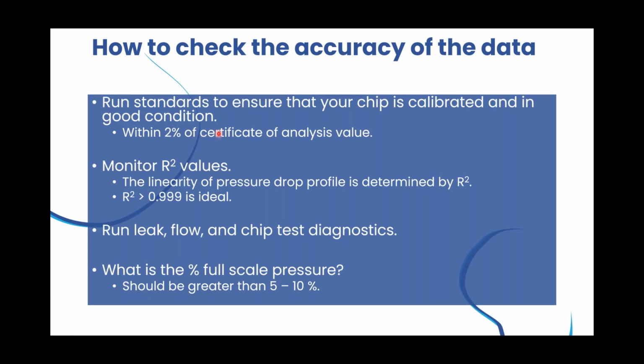Popular standards are medical grade viscosity standard, or MGVS. We use that commonly for Initium and MVROC2. For the Microvisc or Microvisc Pro, it's more common to use oil standards. In using these standards, we calibrate the chip to within 2% of the standard certificate of analysis value.